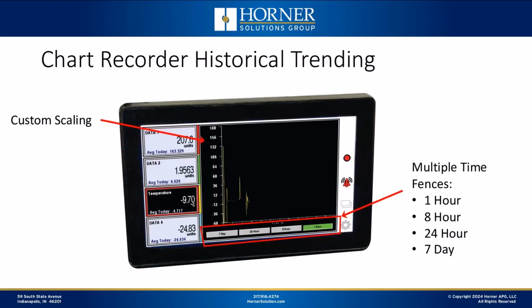And then if we're going to take a look at your process data in a trend view, on the left-hand side you've got your 4 different process values shown from top to bottom in numeric form. And those areas over there to the left double as push buttons, if you will. So if you want to take a look at the trend graph for that third parameter from the top, which I believe is temperature, then when that button is pressed, it's going to show in the trend portion of the display the current trend for that particular process value. And then from a time fence standpoint, along the bottom you can select the time fence for that particular analog value, whether it's 1 hour, 8 hour, 24 hour, or 7 days. So again, you've got a lot of flexibility in terms of how you display the data and what time fence you're using at any given moment.